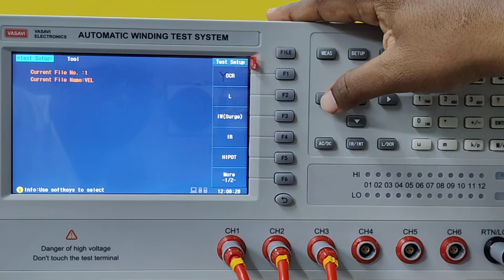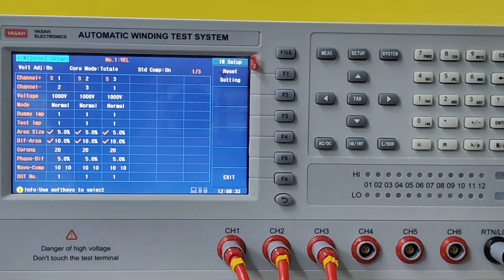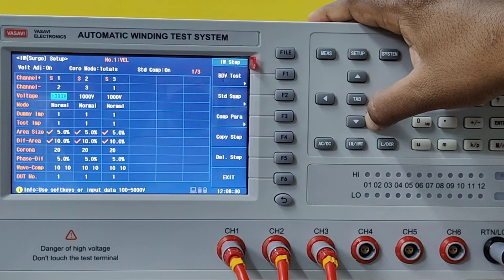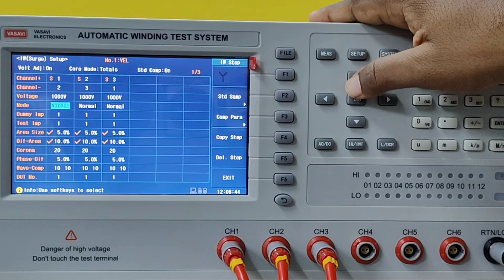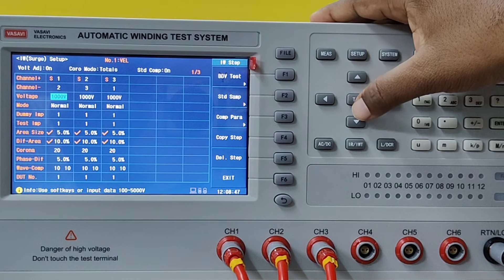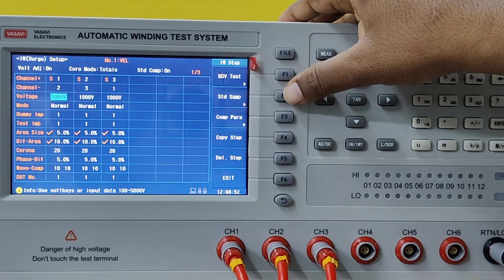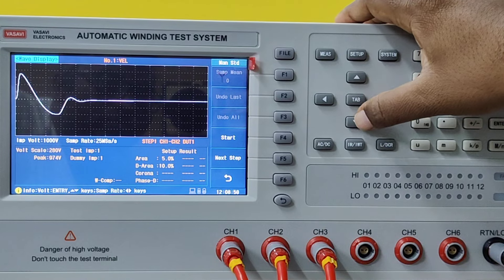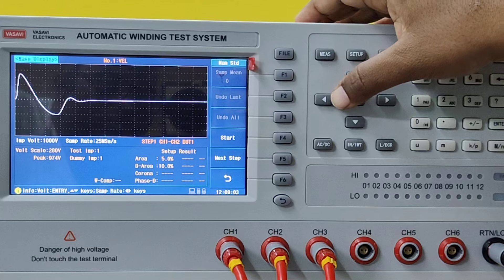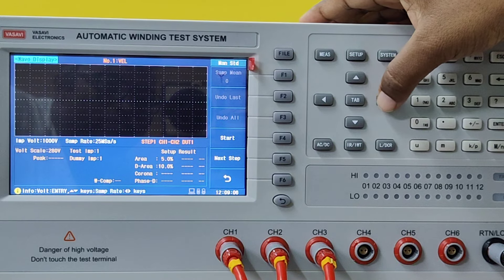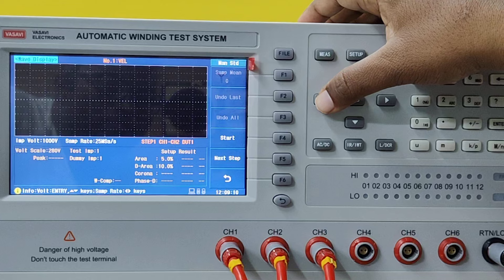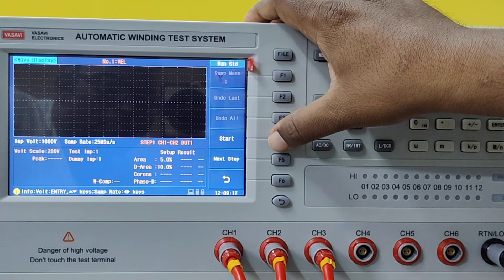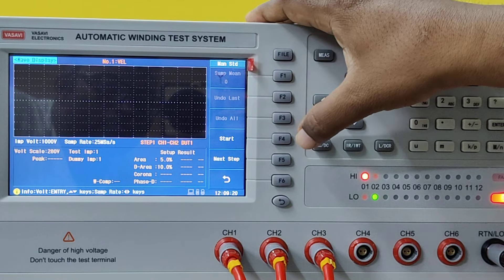Now we will go to the third parameter: impulse winding. In impulse winding, select from the first channel to second channel, and what voltage you want to test impulse at. There is function button F2 for first standard sample test. Press this button. If you want to change the sampling rate, press the left or right button to increase or decrease it. For this, I am setting 25MSa/s. After feeding this, press Start — that is the F4 button. You get the waveform.